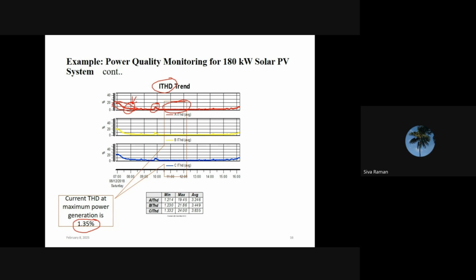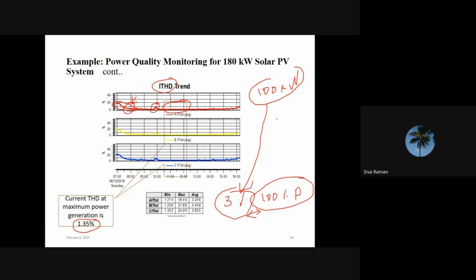Generally, please remember, manufacturers of solar inverters will comply with a current THD of 3% at 100% of active power P. For example, if it is a 100 kilowatt inverter, they will comply with 3% THD at 100 kilowatts only. If it is operating at 20 kilowatts, whether this inverter will produce the same 3% THD is a bigger question mark. Most of the time it will not produce 3%; it will produce closer to 6 to 9%. Please keep this in mind.